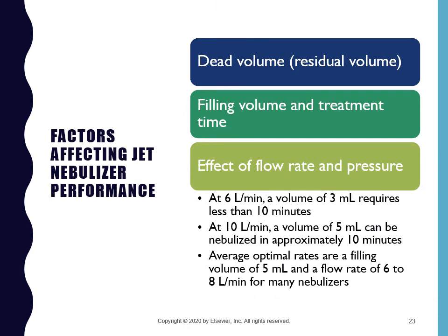So some of the factors that affect jet nebulizer performance are how much residual volume is left, or dead volume, the filling volume, so how much solution does it take to fill it, and how long does the treatment last or take. Some nebulizers, like the teacup neb, take 5 minutes or less. They have very little residual volume, and at flow rates of 6 liters or less, a volume of 3 milliliters is very, very quickly resolved.